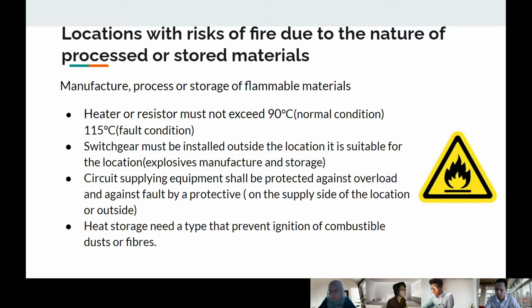Circuit supplying equipment shall be protected against overload and against fault by a protective device, which is on the supply side of the location or outside the location. Heat storage needs a type that prevents ignition of combustible dust or fiber. Heat storage must be done in a careful way, because once ignition occurs in the combustible area, dust can also ignite combustion.